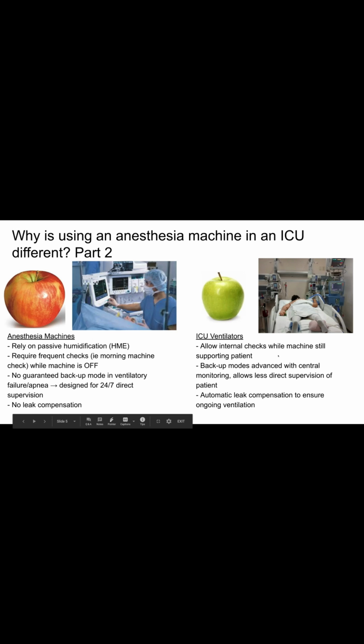ICU ventilators, on the other hand, here we have a prone patient. They do allow internal checks while the machine is still supporting the patient. Therefore, you don't have to disconnect the circuit. They also have backup modes with central monitoring. So a respiratory therapist or ICU nurse or physician can be a few rooms away and still know that there's a patient with a problem with the patient's ventilator. So there's less direct supervision required. And then they do have safety features like automatic leak compensation to ensure that the patient's still being ventilated even if it starts to detect a leak.